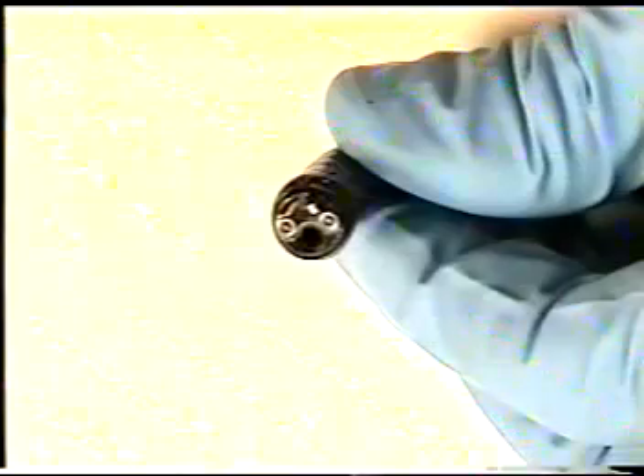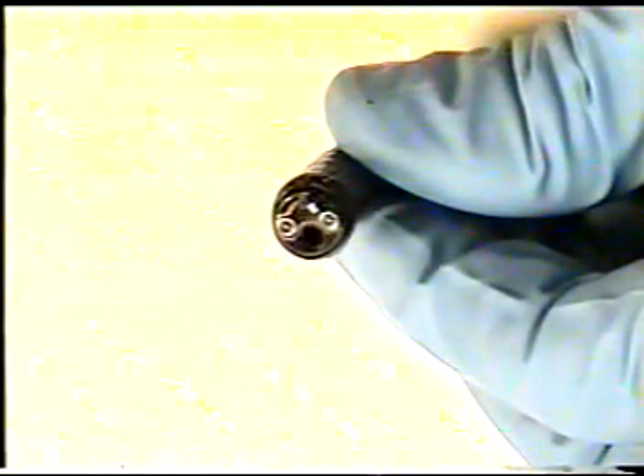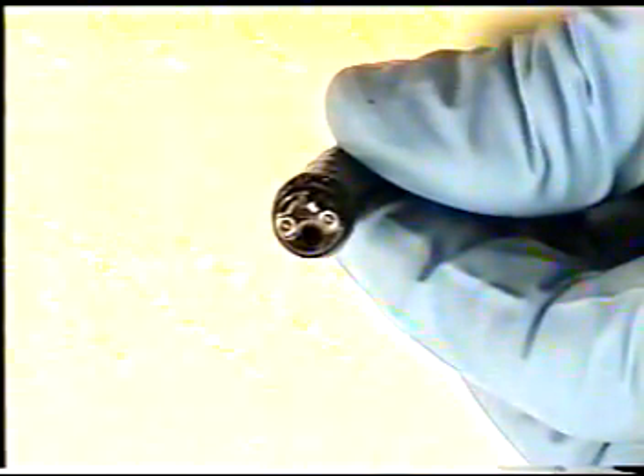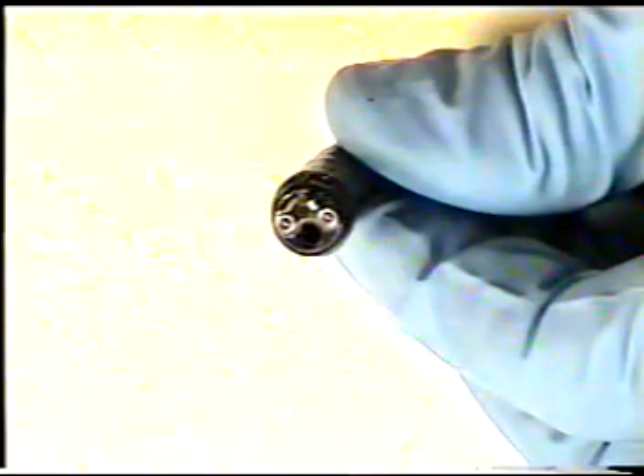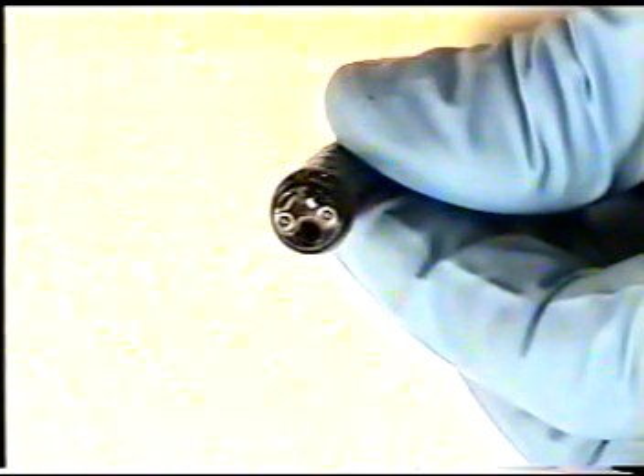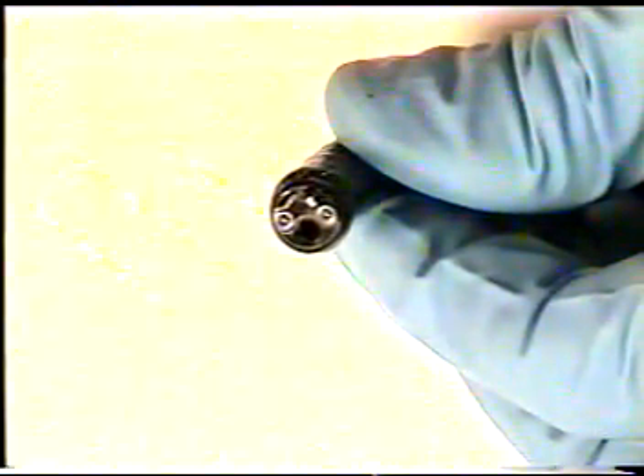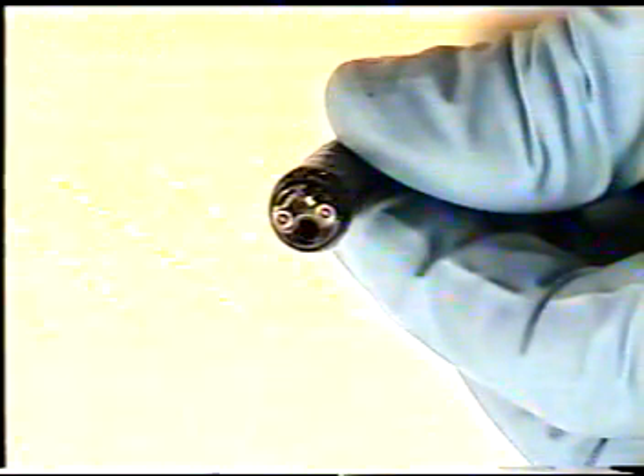Be sure to let black RTV dry for at least 1 hour before testing air-water function. This glue must be dry in order to pass through cleaning and sterilization units. Once you are sure the RTV is dry, hook up the endoscope to a light source, hook up the air-water bottle, and test to make sure that you have the proper air and water.